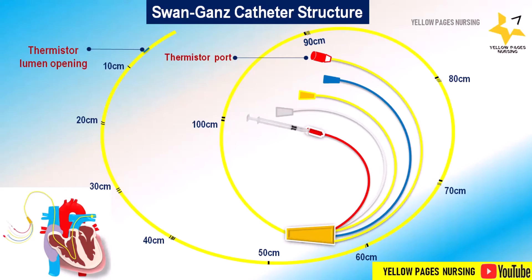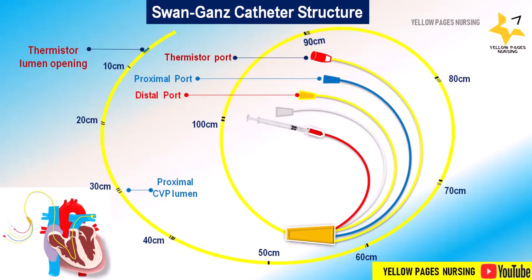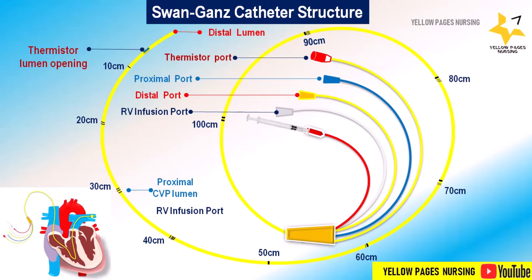Next is the proximal port. The proximal lumen terminates at about 30 centimeters from the tip. Next is the distal port — the distal lumen terminates at the tip of the catheter. Next is the RV infusion port: an optional third lumen called the infusion port, which terminates at about 20 to 30 centimeters from the tip.